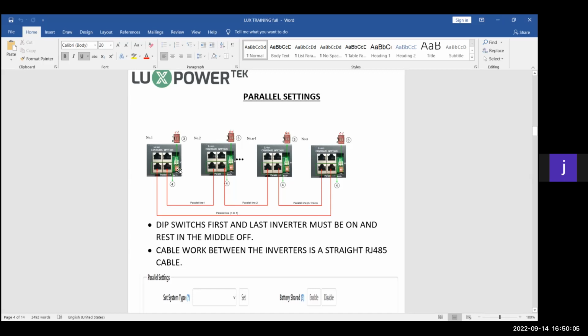Now at the bottom, you will see there's a dip switch box. My new machines will be blue. You will see that the dip switch box is blue. On that dip switch box, on the first inverter both dip switches must be on, and on the last inverter both dip switches must be on, and the ones in the middle must be off. Now, if there's only 2 units, it stays exactly the same: the first unit on and the second one, both of them on. The units using the communication cable plugged into the first and the last port are the ones whose 2 dip switches in the box must be on. This is how the inverter knows which one is the first and which one is the last inverter in the communication chain. If there were 3 inverters, this box would be on, off, on. So this is how the configuration works for the communication between the machines.